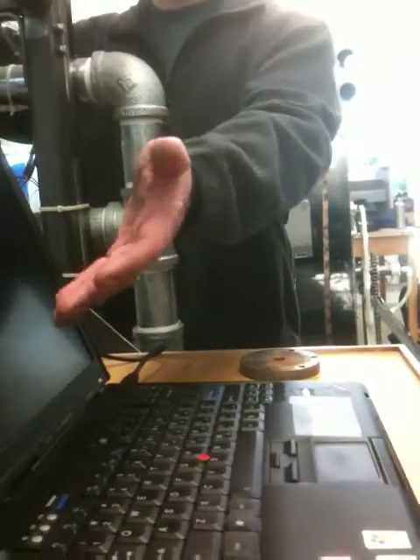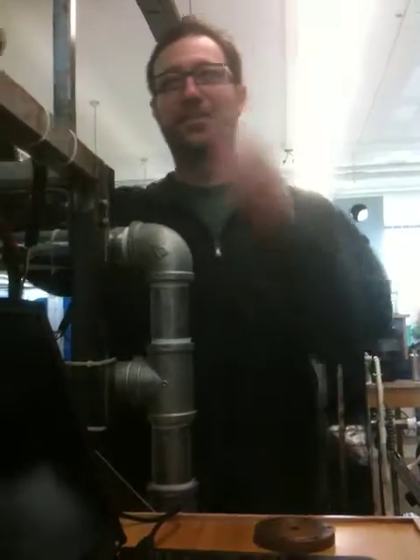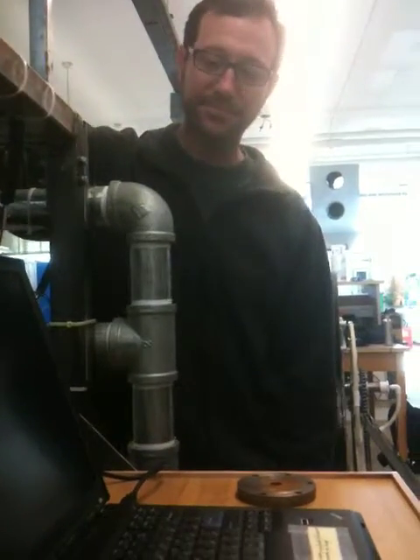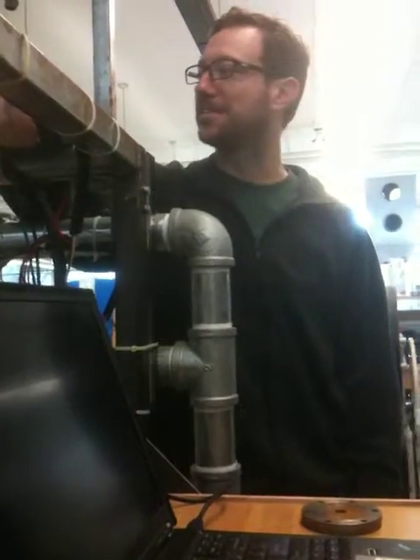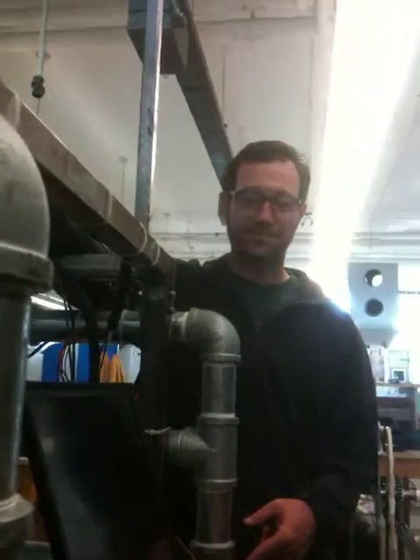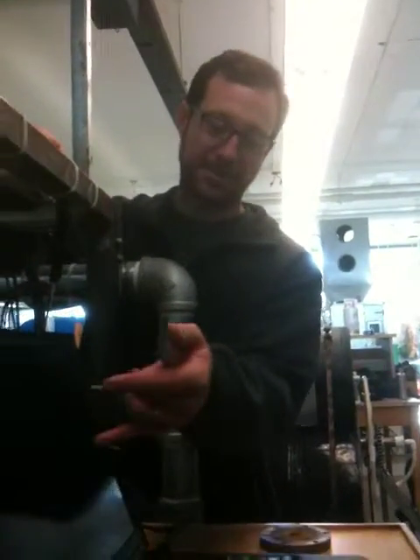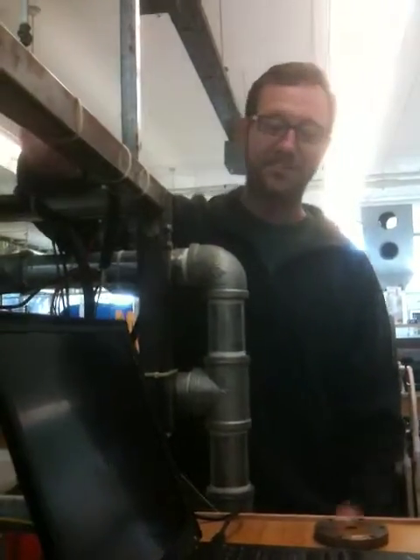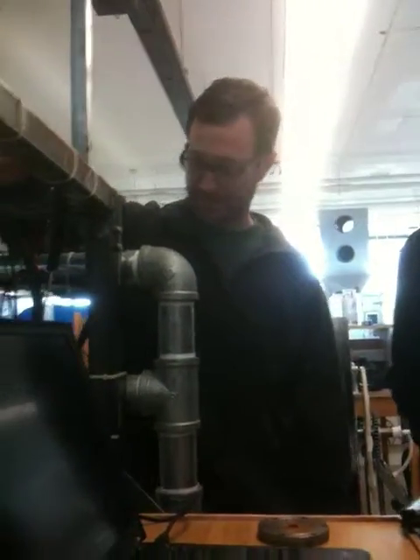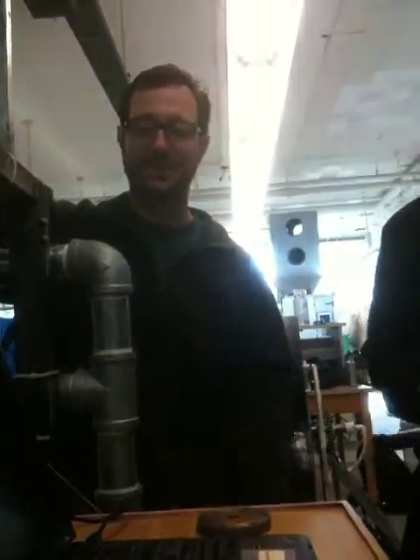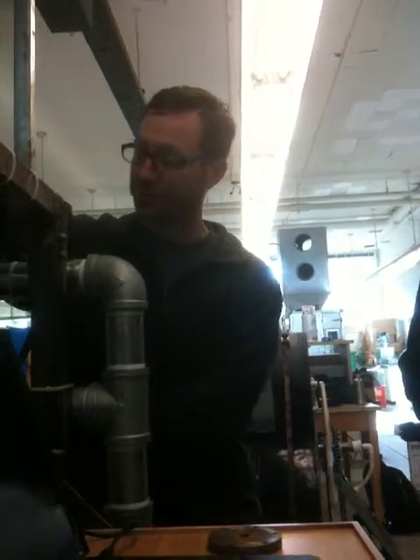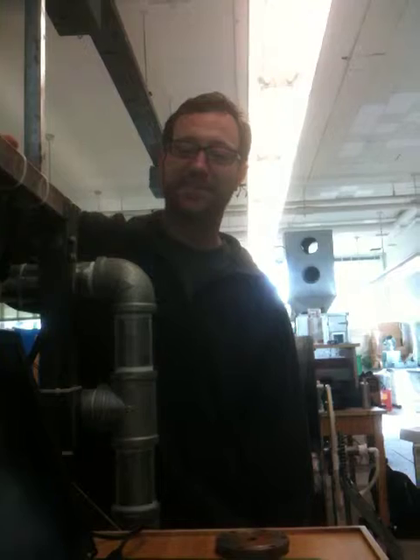You should get no flow, and you'd expect that pressure would be higher because now you're over by the y-axis of that pump curve, as opposed to here's as far to the right on that pump curve as we can get. But that's pretty much it. So somebody move the valve, somebody read these. For this pump part, you just need the pressure across the pump and the flow rate. For the valves, you just need the flow rate and the difference in pressure. And then for these, you just need the flow rate through the magnetic flow meter and the flow rate through this flow meter. Got two different flows.